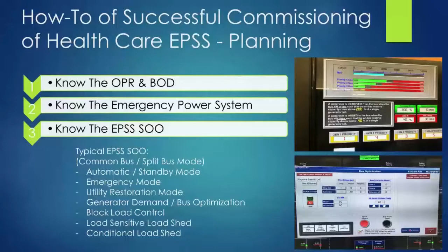Automatic or standby mode, emergency mode, utility restoration mode, generator demand and bus optimization, load control, load sensitive load shed, and conditional load shed — all of these are different functions of the paralleling gear system. You might have ASCO, Russ Electric, or another paralleling gear manufacturer, and the terminology may change on what they call how their systems operate, but they all operate very similarly, with very similar functionalities.